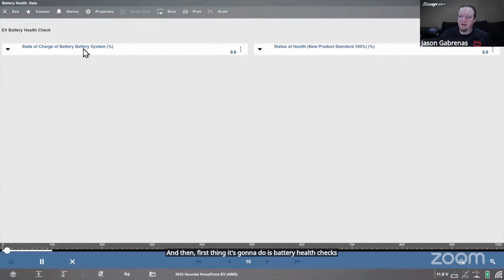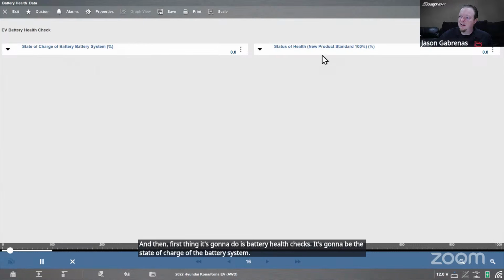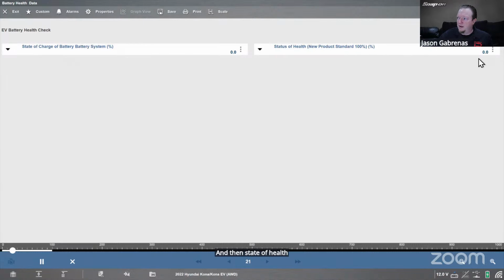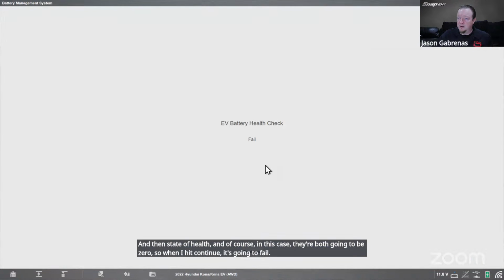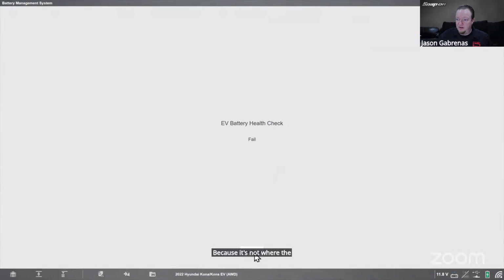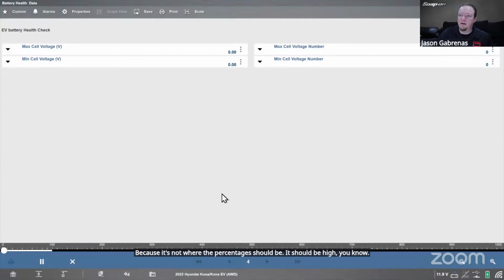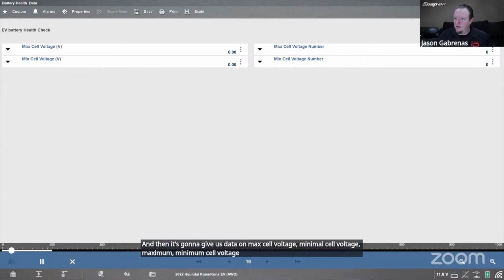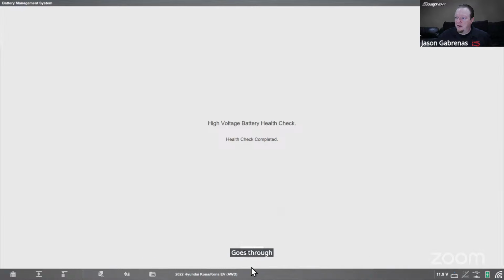It shows the state of charge of the battery system percentage-wise, and then state of health. In this case they're both going to be 0, so when I hit continue it's going to fail because it's not where the percentages should be - it should be high, above 80 or 100. Then it gives us data on max cell voltage, minimum cell voltage, and the max and minimum cell voltage numbers, like we said before. Goes through that - health check complete.